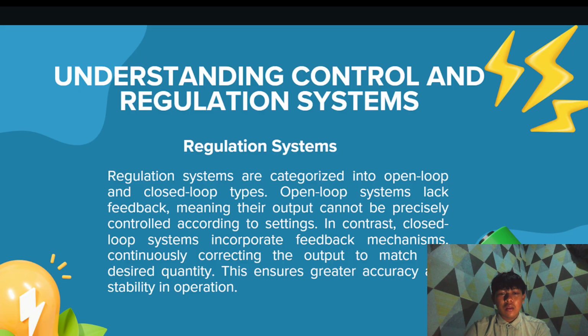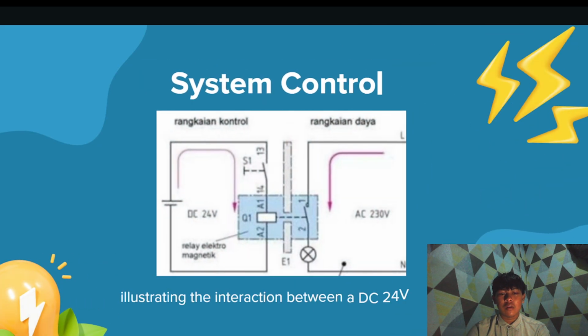Regulation systems are categorized into open loop and closed loop types. Open loop systems lack feedback, meaning their output cannot be precisely controlled according to the setting. In contrast, closed loop systems incorporate a feedback mechanism, continuously correcting the output to match the desired quantity. This ensures greater accuracy and stability in operation. And this is the illustration of the interaction between a DC 24-volt control circuit and an AC 230-volt power circuit via a relay.